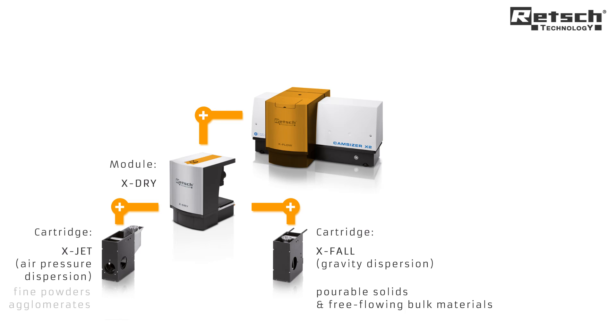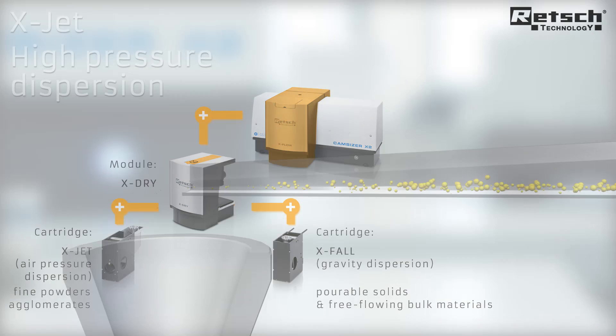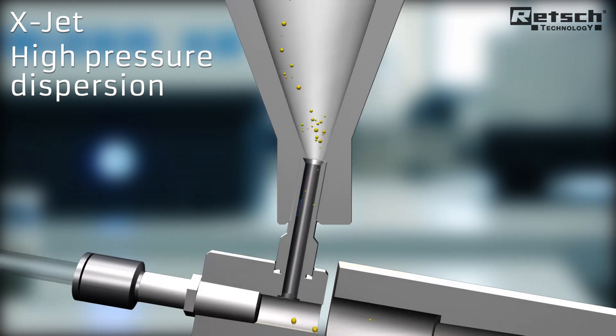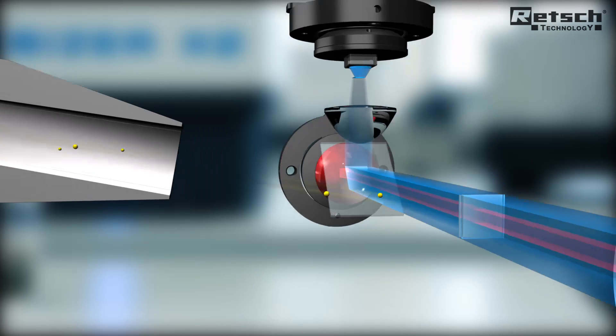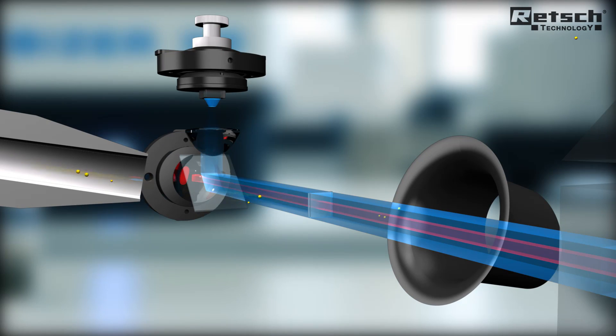The high-pressure cartridge X-Jet is suitable for fine powders and agglomerated material. The sample is dispersed in an airflow which ensures that agglomerates which would falsify the measurement results are broken down prior to detection.